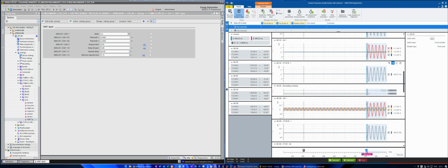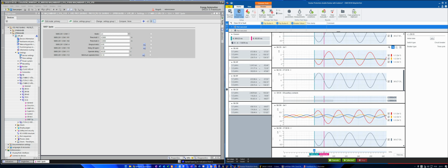So for example, I put the two signals here together. I will zoom in and take here. For example, you can see that my current in my bay starts here, but my circuit breaker contact says that it is closed just here. What is the interval of time that we have between here? Just 50 milliseconds. This is very common to happen, and this is not a big time. I can say that it is a very small time, and it happens when you close in a fault.